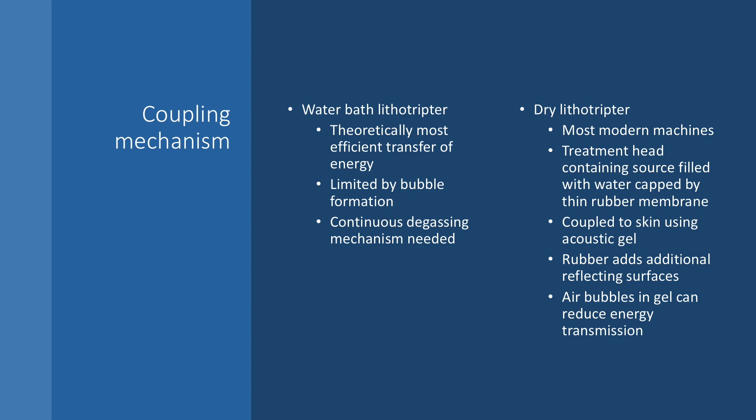Most modern lithotriptors don't use water baths — they are what we call dry lithotriptors. In this type of setup, there is a treatment head which contains the shockwave generator, usually either an electromagnetic or piezoelectric generator, and this treatment head is filled with water, capped by a thin rubber membrane. This membrane is then coupled to the patient's skin using acoustic gel. This is less efficient in terms of coupling than the water bath, because the rubber cap adds additional reflecting surfaces and air bubbles within the acoustic gel can again reduce energy transmission.